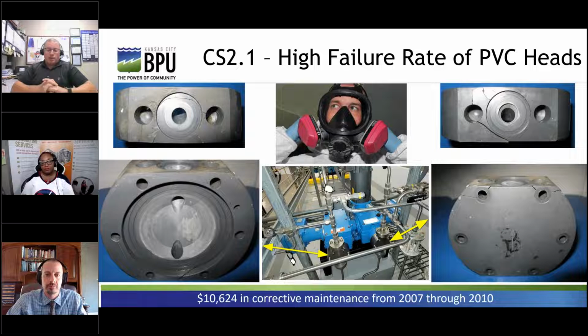So for maintenance costs, Maximo started collecting maintenance data in 2007, missing corrective maintenance and PM maintenance for anything before that. However, from 2007 through 2010, we used 8 of these PVC heads between both ammonia metering pumps for a combined total repair cost of $10,624 in parts and labor for that specific failure mode.